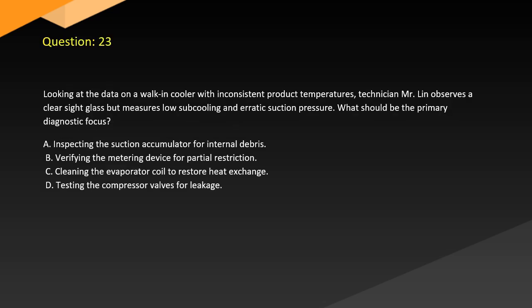Question 23. Looking at the data on a walk-in cooler with inconsistent product temperatures, technician Lynn observes a clear sight glass but measures low subcooling and erratic suction pressure. What should be the primary diagnostic focus? A. Inspecting the suction accumulator for internal debris. B. Verifying the metering device for partial restriction. C. Cleaning the evaporator coil to restore heat exchange. D. Testing the compressor valves for leakage.